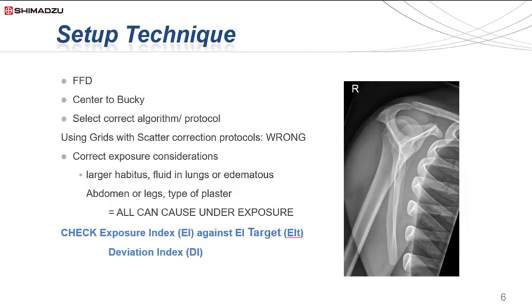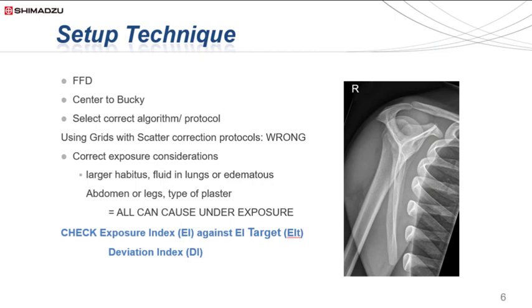To avoid underexposure whilst using AEC, ensure that both the tube and the patient's anatomy to be imaged is positioned in the centre of the Bucky. Take for example a lateral shoulder projection — if the shoulder is positioned too lateral or too high on the erect bucky away from the centre AEC sensor, then the resultant image will have an adequate exposure of the lungs and ribs but an underexposed image of the scapula and humerus.